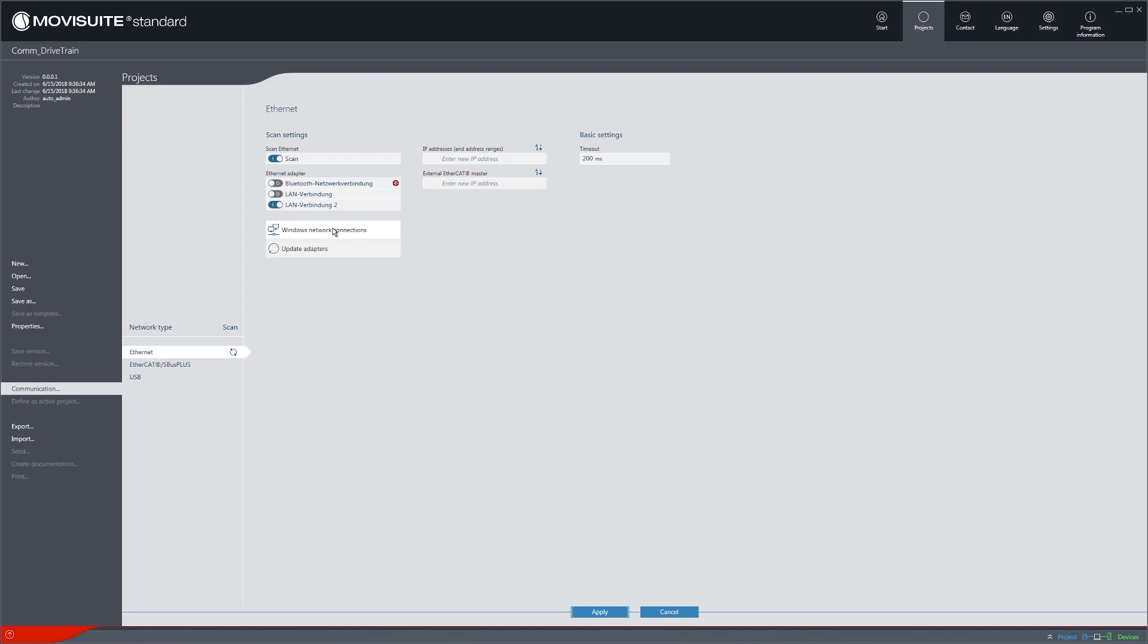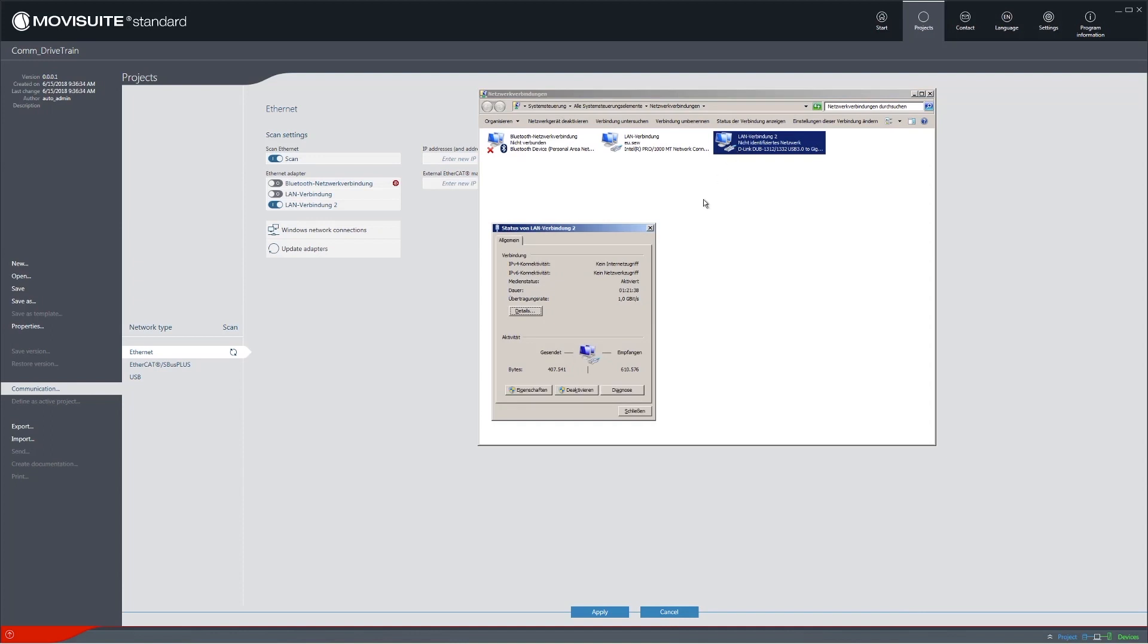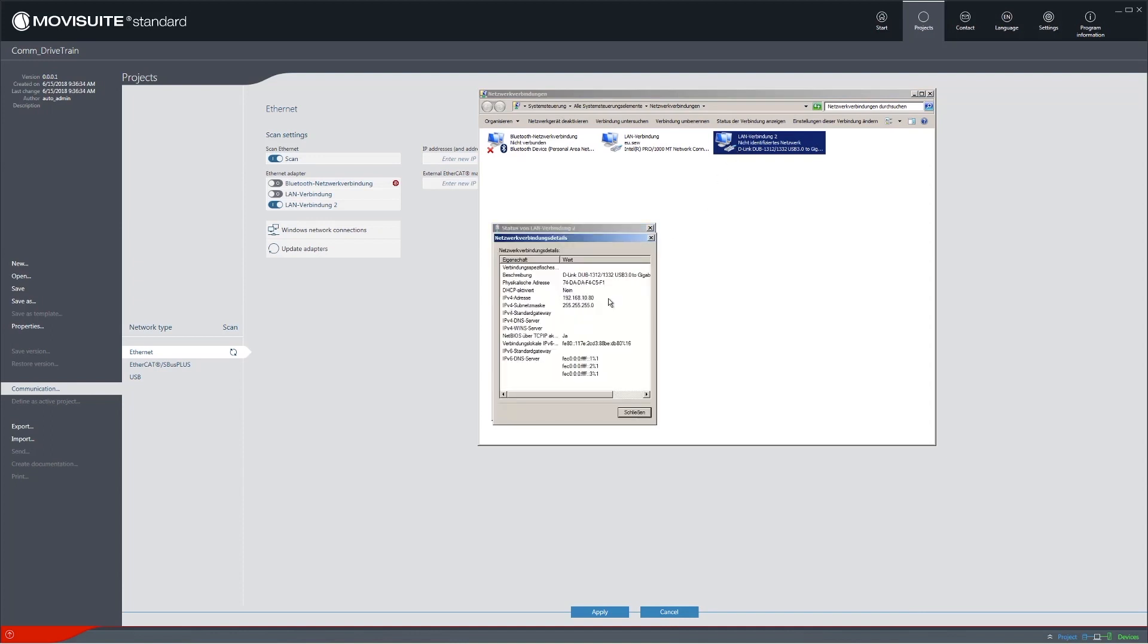Every SEW EuroDrive controller has a default IP address of 192.168.10.4. Since the PC is currently connected directly to the SEW EuroDrive controller via a network cable, you will need to set a fixed IP address on the PC, which is 192.168.10.80.